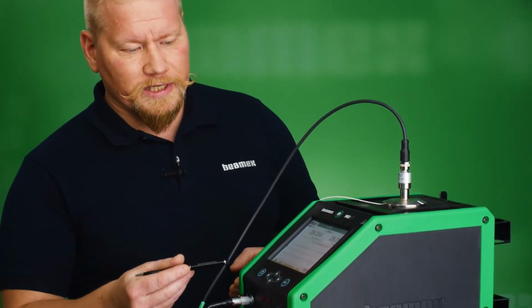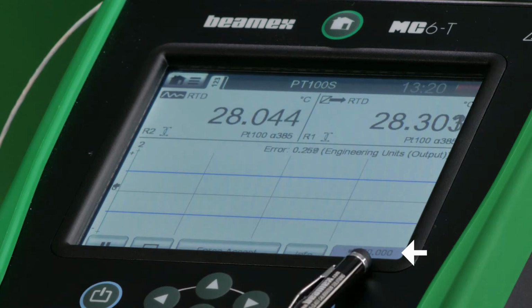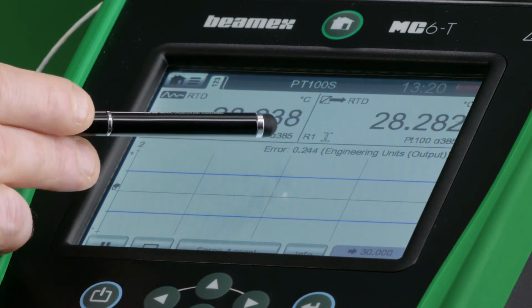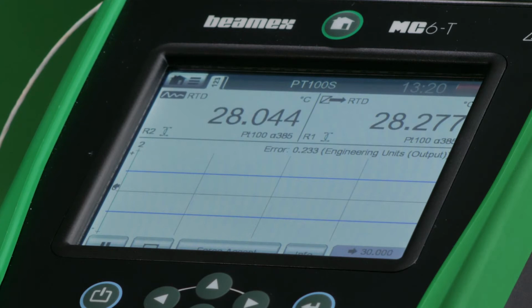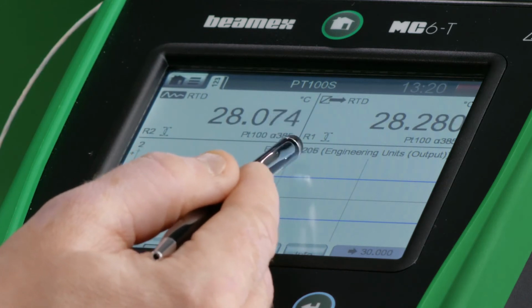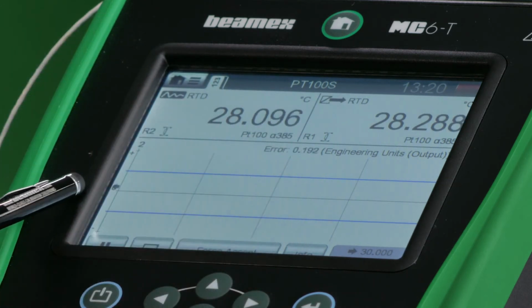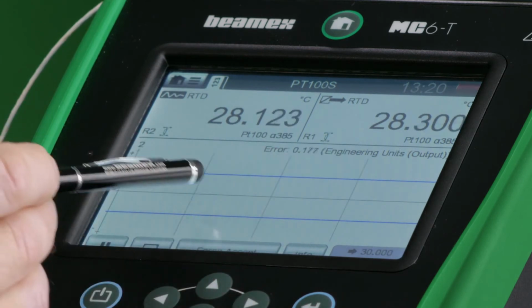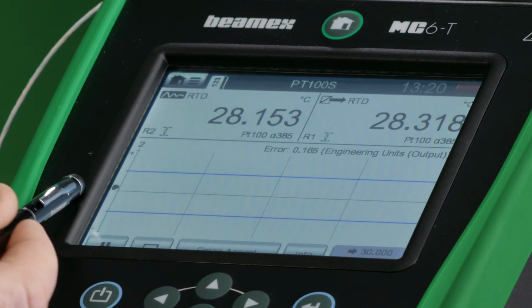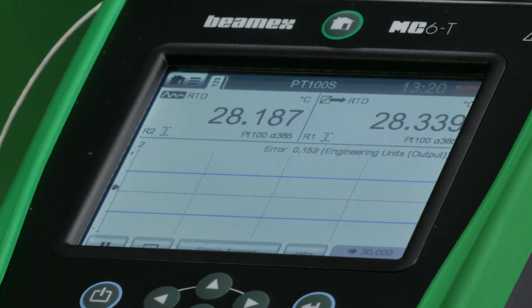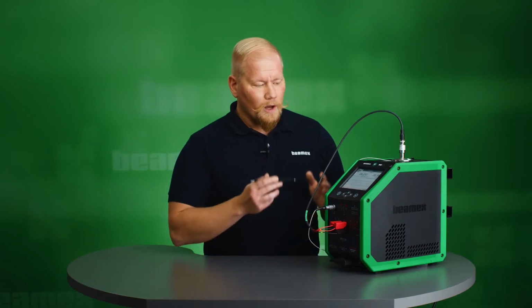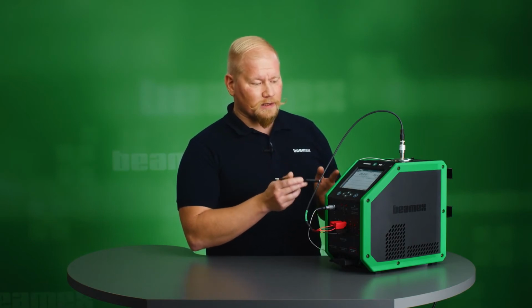And I have now started my calibration sequence. What you see here on the screen is, first of all, my set point. The first point is going to be 30 degrees Celsius. And the MC6-T is constantly calculating the error, comparing the reference to my sensor values and showing the error value, but also a graphical view. So what you will be seeing here is a green dot traveling between these 2 blue lines. If it's below or above, it's going to be a failed calibration. As long as it's inside, it's going to stay green and be a pass calibration. We'll now let it continue and take the first set point.